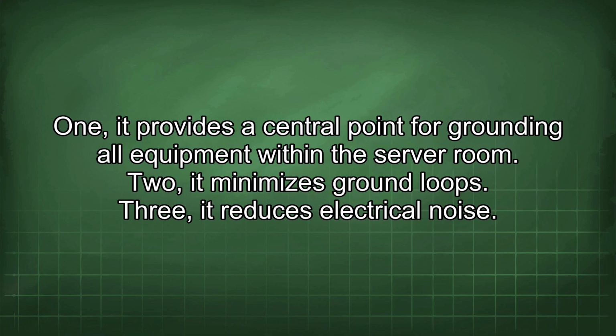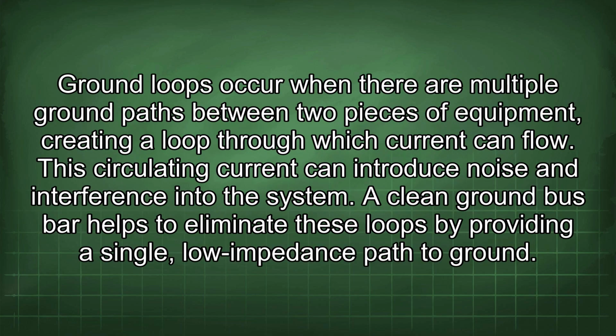1. It provides a central point for grounding all equipment within the server room. 2. It minimizes ground loops. 3. It reduces electrical noise. Ground loops occur when there are multiple ground paths between two pieces of equipment, creating a loop through which current can flow. This circulating current can introduce noise and interference into the system. A clean ground bus bar helps to eliminate these loops by providing a single, low-impedance path to ground.